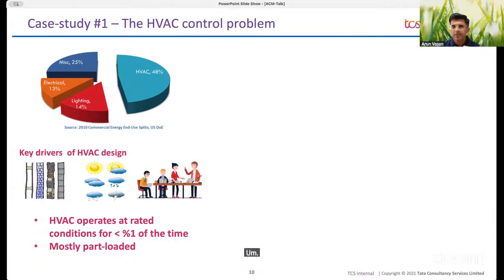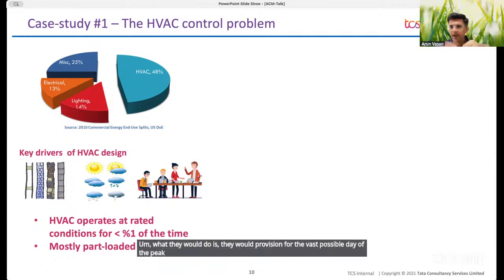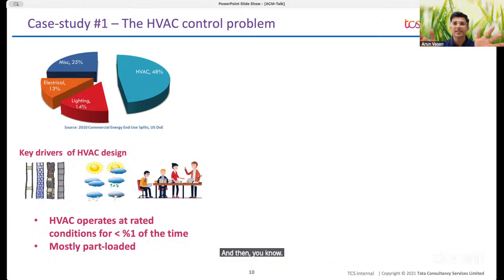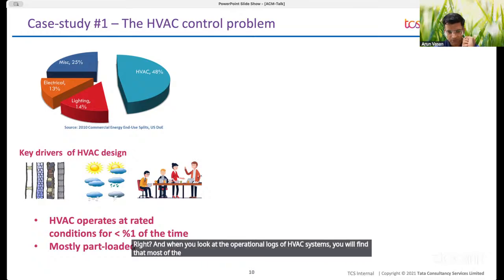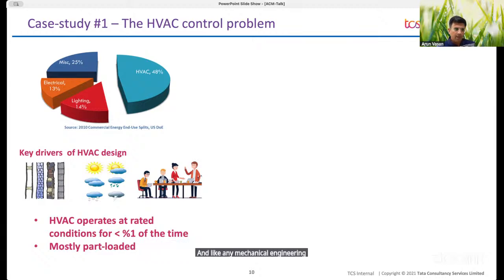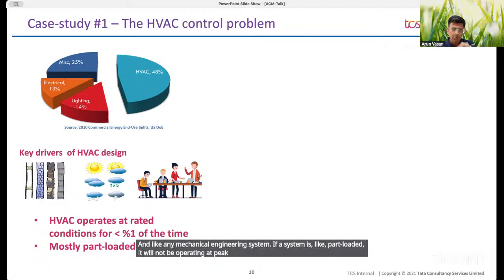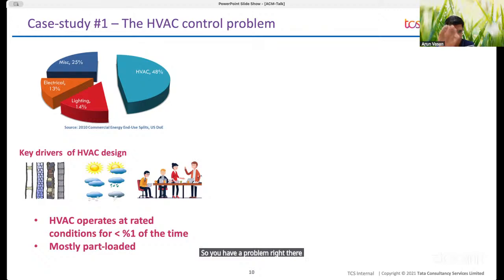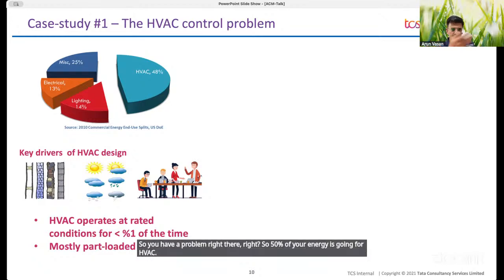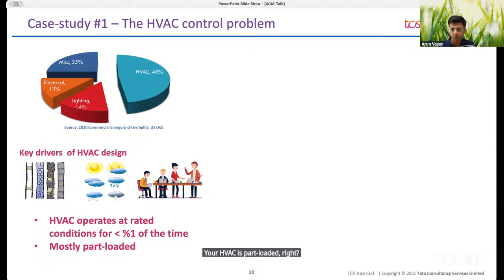What they would do is provision for the worst possible day of the peak summer season, and then design the HVAC system for that worst case condition. When you look at operational logs of HVAC systems, you'll find that most of the time these HVACs are partly loaded. And like any mechanical engineering system, if it's part loaded, it will not be operating at peak efficiency. So you have a problem right there — 50% of your energy is going for HVAC, and your HVAC is part loaded. Can we do something better?